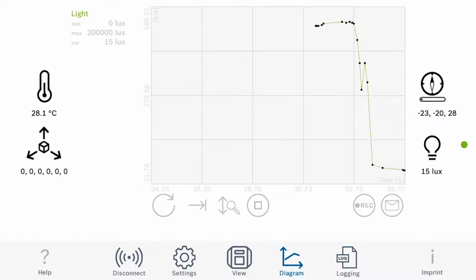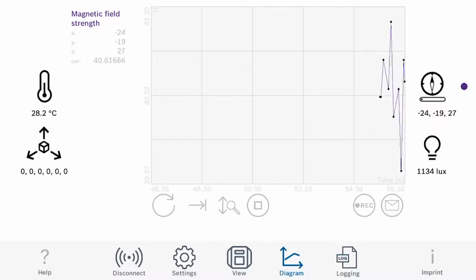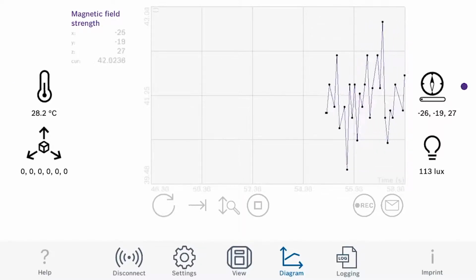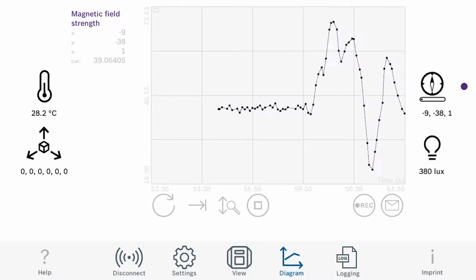The temperature sensor identifies temperature changes and instrument drifts, helping you to measure the temperature profiles of your equipment to then benchmark the performance. The magnetometer identifies current peaks and magnetic disturbances outside your selected range. The accelerometer records shock and vibrations up to 6.4 kHz.